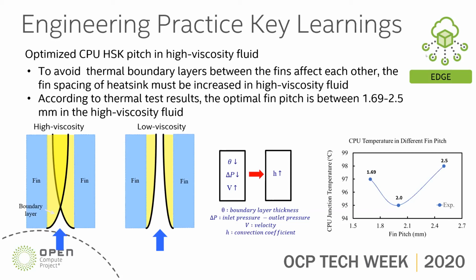The main goal of the heat sink design is to reduce the boundary layer interface, which reduces pressure drop and increases flow rate to improve overall heat transfer efficiency. Based on our thermal test results so far, the optimal fin pitch should be between 1.69 to 2.5 millimeters with our first selected liquid.